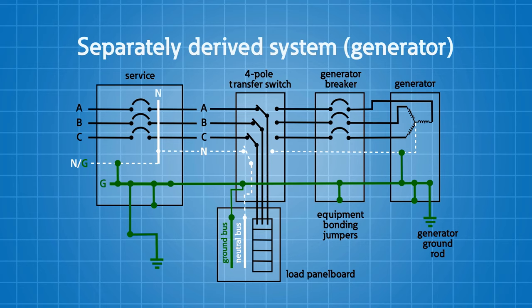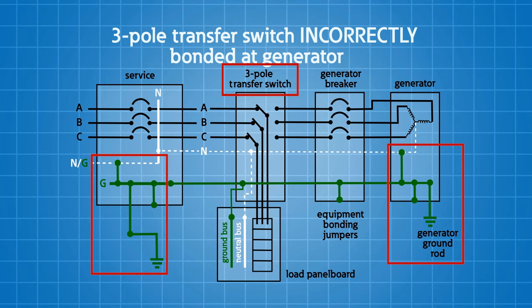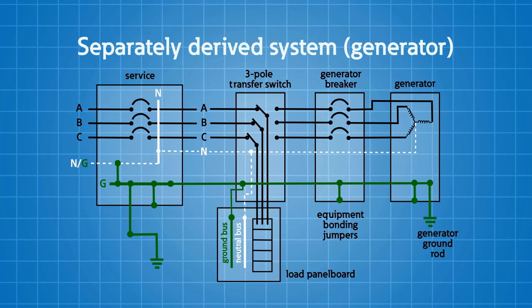Understanding that this action creates a separately derived system is important because it drives what you do in the transfer switch. If you bond neutral to ground in the generator and establish a separately derived system, you're going to need to switch the neutral in the transfer switch, meaning you'd need a four-pole transfer switch instead of a three-pole transfer switch. If you're bonded in the generator but not switching the neutral, you have two separate areas where the neutral conductor is being bonded, which can cause circulating currents and cause GFCIs or ground fault protection equipment to not work correctly. A simple fix if you have a three-pole transfer switch and bonded the neutral in the generator is to just lift the bond in the generator — your generator instructions will tell you how.